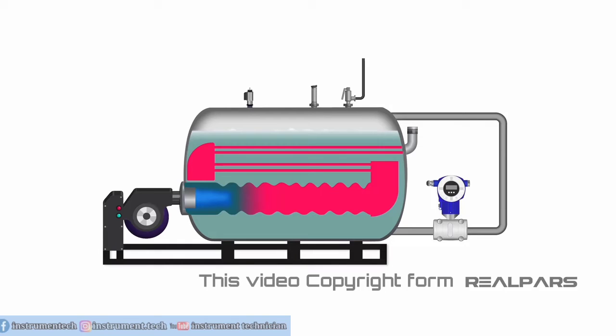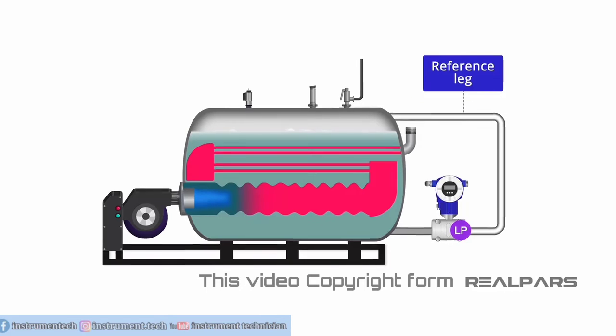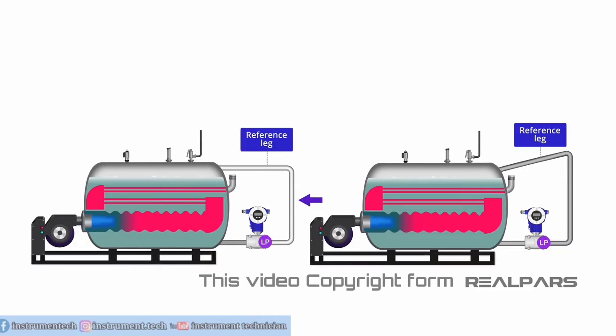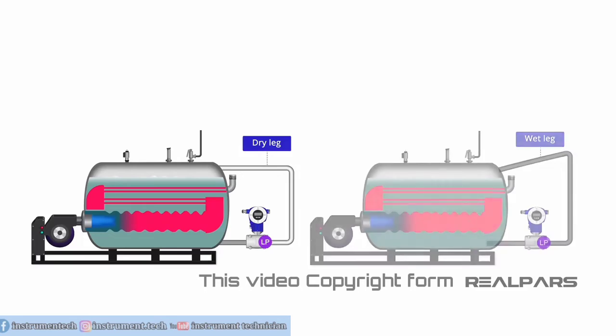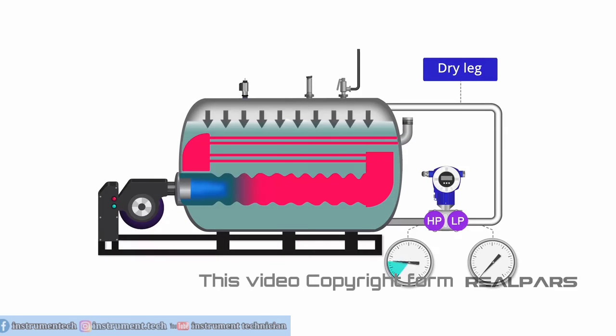We can compensate for the vapor pressure by connecting the low pressure side of the differential pressure transmitter to the top of the vessel through a pipe referred to as a reference leg. The reference leg may be dry or filled with liquid. If the reference leg is dry, it is commonly referred to as a dry leg, and if the leg is filled, it is commonly referred to as a wet leg. In a dry leg system, the vapor pressure is applied to the high pressure and the low pressure sides of the differential pressure transmitter. The same pressure applied on each side basically cancels each other out.